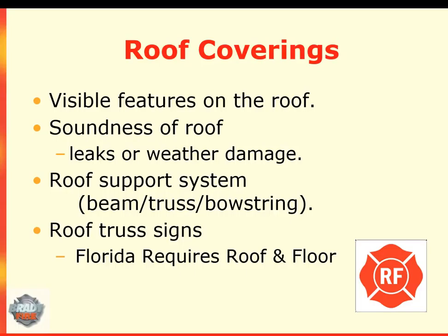Examine fire protection features visible on the roof, including the location of firewalls and hazardous exhaust systems and ventilators. Examine the smoke exhaust system or fire vents if applicable. Examine firefighter roof access and determine the roof covering. Serious leaks in the roof can cause structural damage and may result in early collapse of the building in a fire. If the roof is supported on steel or wooden trusses or steel or wooden I-beams, it may require identification signs at the main entrance for firefighter safety. Florida requires firefighter warning signs for truss construction.